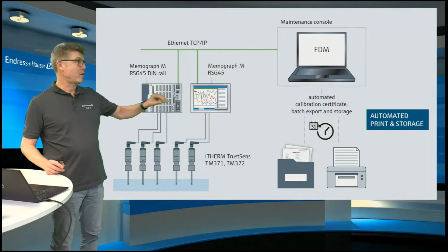The next question is, okay, we create calibration certificates every time we have the calibration process, where should we put all of these documents? And we offer a variety of solutions. The total one is that, like we did here, you can connect a number of these TrustSens instruments. They communicate using the HART protocol with a data manager. This data manager reads out the calibration information and can transmit it using the internet protocol to a software which generates a safe database which cannot be manipulated, and additionally it can generate PDFs which can be stored somewhere on the file server.